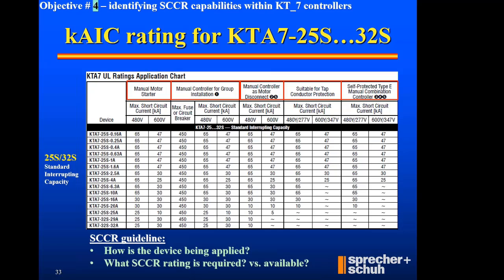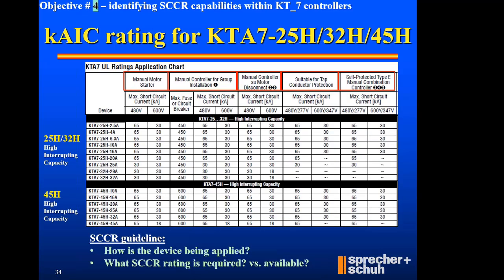However, as you notice, when I get into the higher amps of 20, I'm only getting 10 KAIC at 20. A 25, nope, don't get type E. 29 and 32, nope, don't get type E. So what would I do? Let's move to the next page to a 25H, 32H, high interrupting capacity.